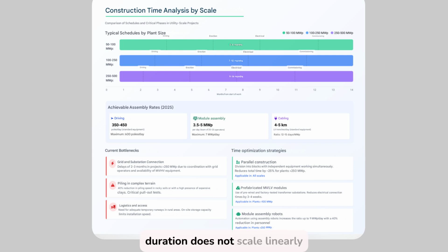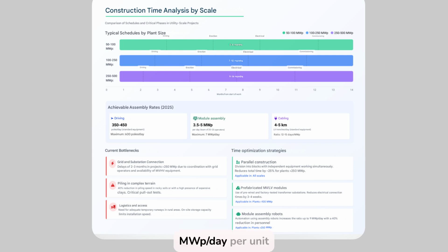Schedule duration does not scale linearly with capacity. Therefore, parallelization and prefabrication strategies are necessary. Below, we see actual productivity metrics for 2025. Pile driving, between 350 and 450 posts per day, maximum 600 with advanced equipment. Module assembly, 3.5 to 5 MWP per day per unit, maximum 7 MWP per day if automated. LV/MV cabling, between 4 and 5 kilometers of trenches per day, estimated rate 12-15 days per MWP. These rates help calculate actual schedules based on the number of units, shifts, and logistics.